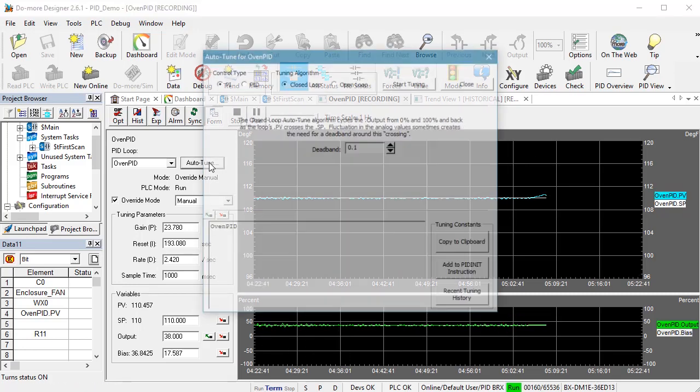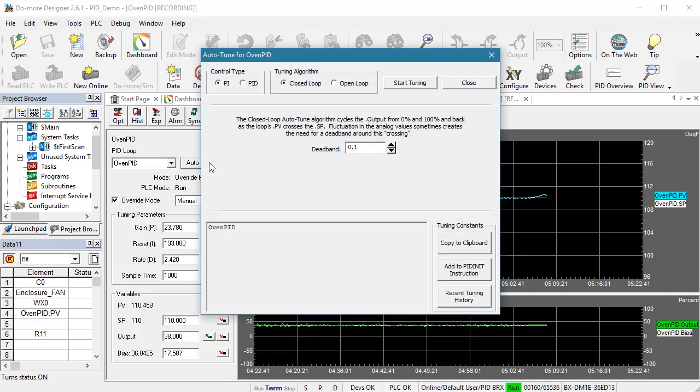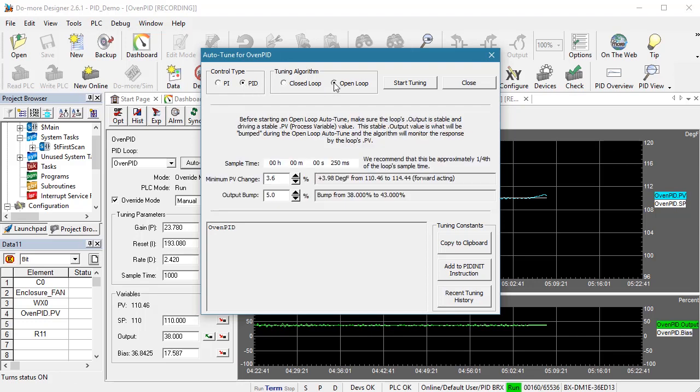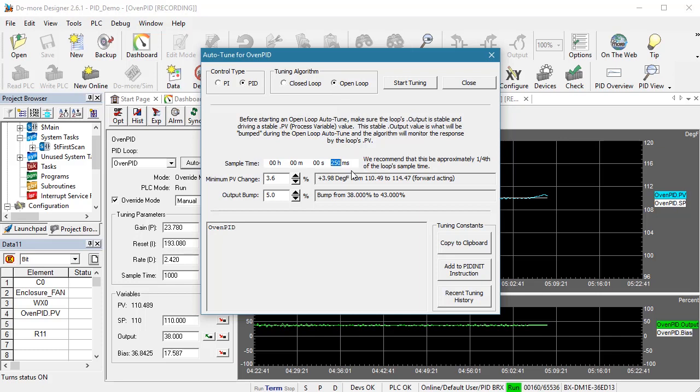We want the PI and D option so we can compare apples to apples with the previous test and we want open loop tuning. We have some new options to look at. First, we need to specify the rate at which we want the PLC to sample the data. You want this to be around 4 times the speed of your PID loop. We know our PID tends to run around 1000 milliseconds so I will put 250 milliseconds here.